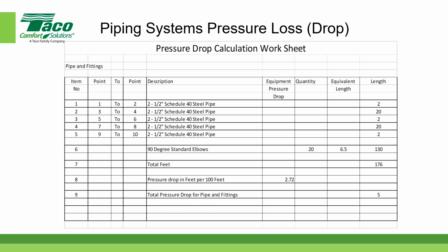Okay, so from point 1 to point 2, that's item number 1 in my little chart. I've got 2.5-inch Schedule 40 steel pipe, and the length is 2 feet. I figured out the length on that. Perhaps I had a scale drawing and I measured it. Or in AutoCAD, if you're doing your drawings to scale, you can just click from point to point and find out the exact length. So let's assume in this case it's 2 feet.